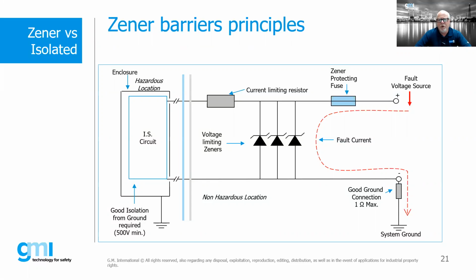The reason we have multiple Zener diodes in many IS barrier products is redundancy - all these Zeners are tested and should open up at a certain voltage, but if one fails, we have a backup, and if two fail, we have another backup. This is actually a double redundant Zener diode barrier, which is required when devices are located in a zone 0 area - so we have three Zener diodes located in a Zener barrier.